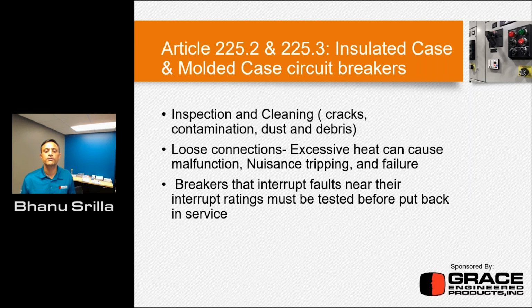Breakers that interrupt faults near the interrupt rating must be tested before you put them back in service. The reason they're calling this out is that breakers are not meant for, say, 5 faults. Whenever you use these breakers, they're not rated to handle 5 faults. They're just tested for 2, and they're designed to handle only 1. So when these devices are handling faults at their max, make sure they are tested afterward, to make sure the functional integrity is maintained, okay?